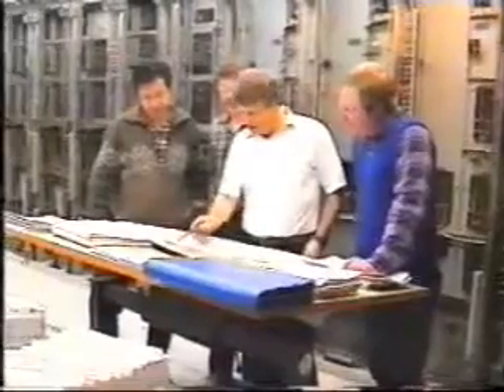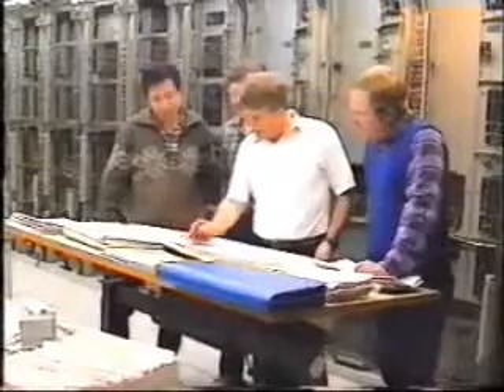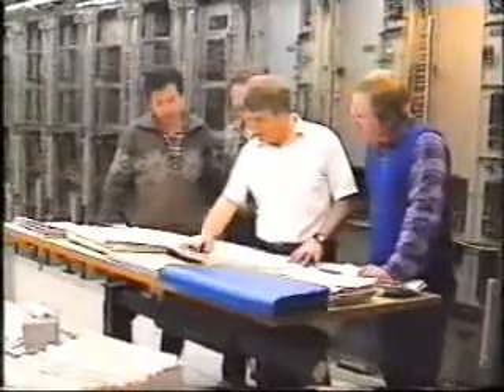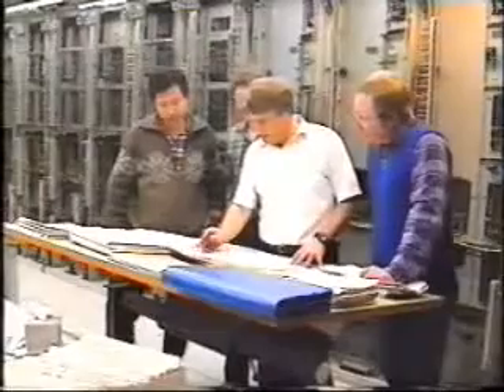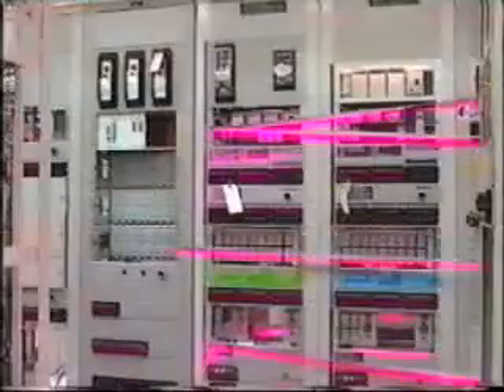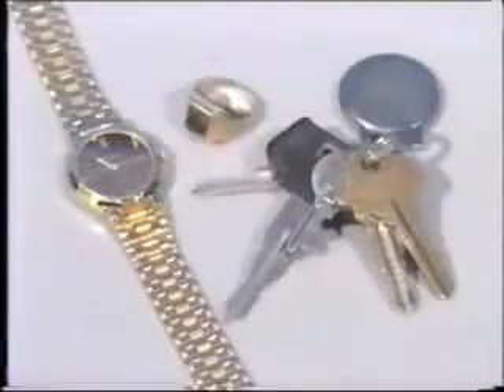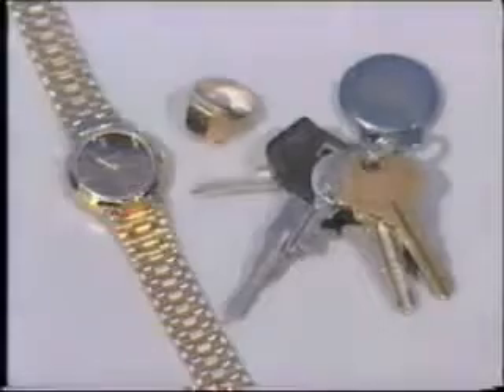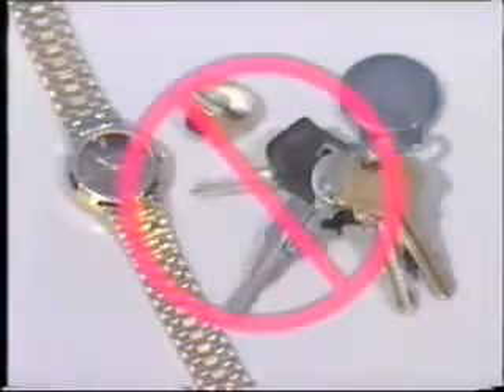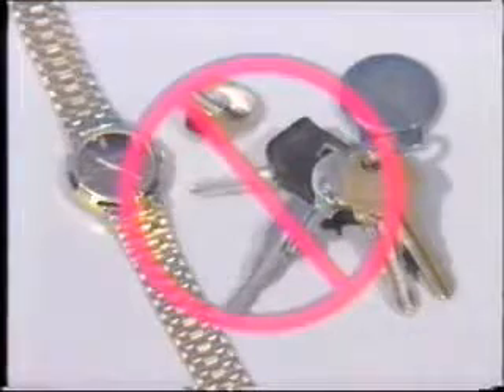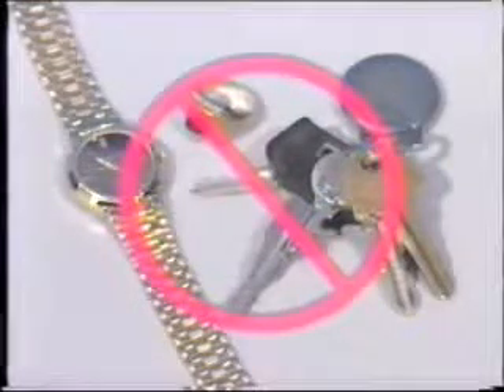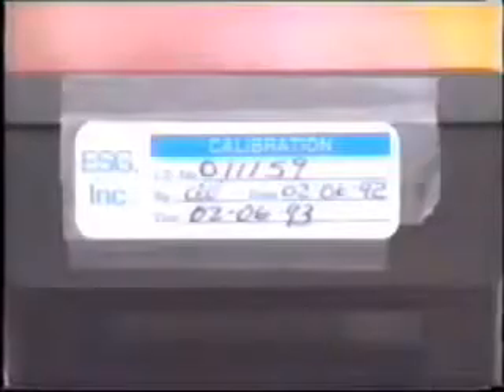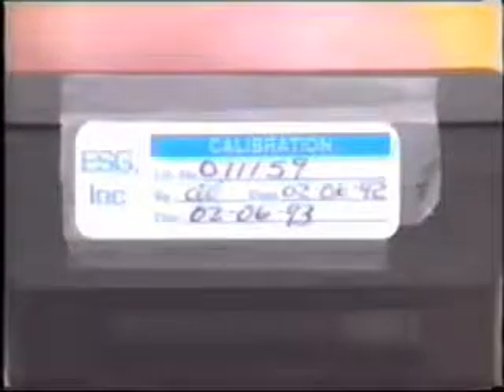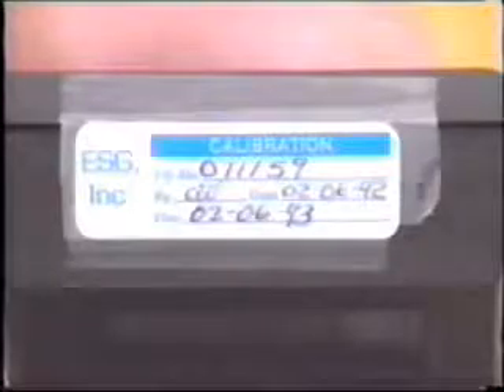Before commencing work, the test crew should review the scope of work to be performed, check prints, and identify potential hazards. For example, if a test voltage or current is to be applied, any secondary circuits and exposed connections should be isolated and tagged, as they may become energized. Also, it is good practice to remove personal items such as wristwatches, rings, keys, and so on, as they have been known to contact live circuits in delicate relay work and cause damage and perhaps injury. When performing functional testing, be sure that your test instruments are calibrated and in good working condition.